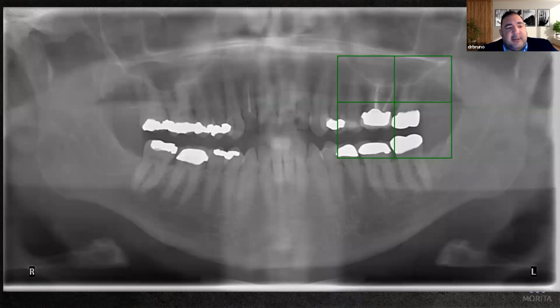And the challenge that I see in lots of imaging centers and lots of offices, they're using Morita and they're using the panoramic scout. It's this situation here where 50% of the scan is composed of information that can create scatter. So think about this for a second. Every time that you see this box, you're talking about 2 centimeters to the right, 2 centimeters to the left, 2 centimeters to the top, and 2 centimeters down, because the volume is 4 by 4. If we were to evaluate this, just for a simple math evaluation, 2 centimeters or half, 50% of the scan is just crowns that can truly interfere with image quality.